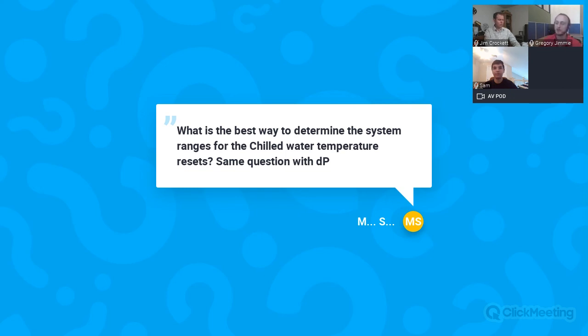I would say a general rule of thumb would be take your end of the line valve, the last chilled water valve in the system. What's that valve's pressure differential requirement? And then you can measure it at that valve. So say it's a 4 PSI valve. You can go take a pressure reading at that valve, start stepping down your pressure set point, whether that's measured remotely or at the plant. It's kind of arbitrary, but just some reference point, start stepping that down. And then when your measurement at the end of the line valve is close to 4 PSI, so maybe you want to leave a little extra at 4.5, that would basically correlate to your minimum DP on the reset.